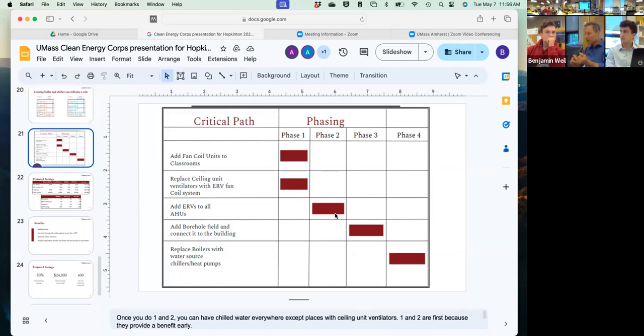Right now you have a hot water coil and a chilled water coil. If there's an ERV, your hot water coil is large enough already to run 105 degree water, because the ERV is taking that load off of it. That also increases its total functional capacity so that we're able to provide more heating or cooling to the gym, for example. Assuming, based on what we saw, that it's all basically functioning fine, you're probably not going to replace them. But if you've got a different capital improvement approach and you just declare things end of life and then replace them, then yeah, the thing to do is just to specify exactly what you want.